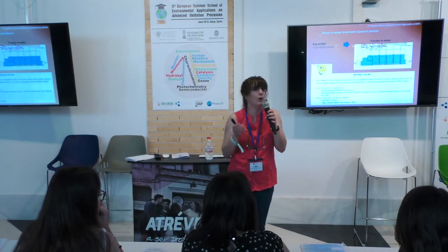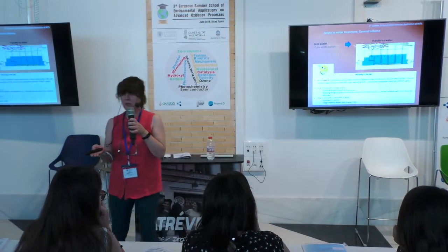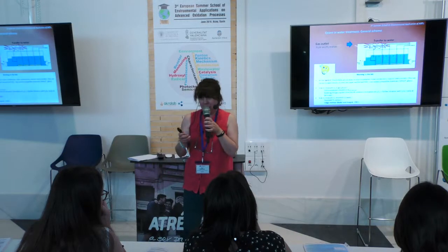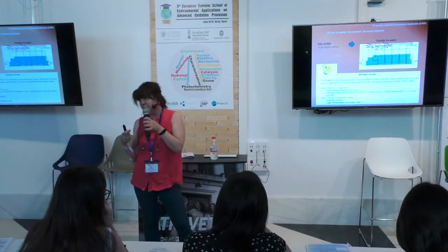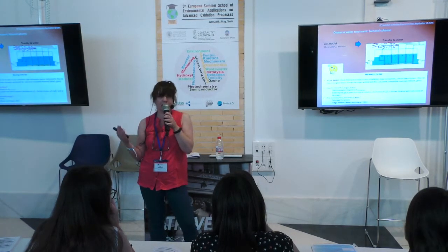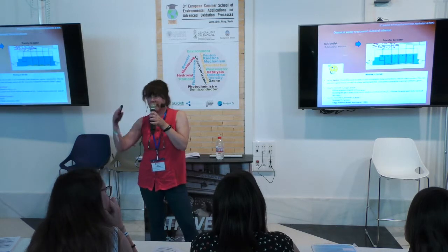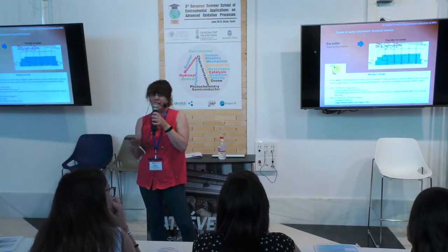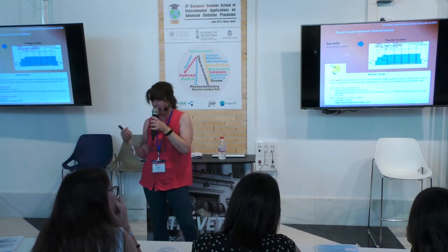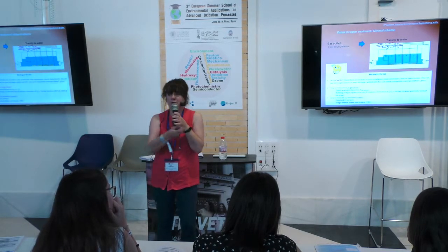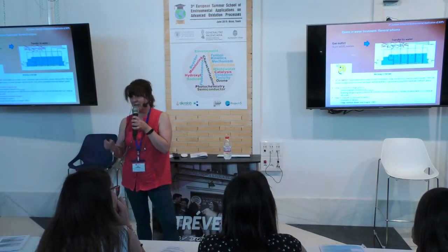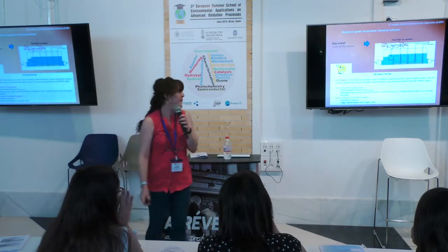Also use ozone-compatible materials, such as Teflon, that is PTFE, or glass. We had been using diffusers made of stainless steel. During the ozonation process, as in other processes, you know that carboxylic acids are formed at the end, oxalic acid among them. Oxalate forms a complex with iron, ferrioxalate, so we noticed that some iron was leached in the presence of oxalic acid from our diffuser. So now we have changed, and we are using ceramic ones, okay?